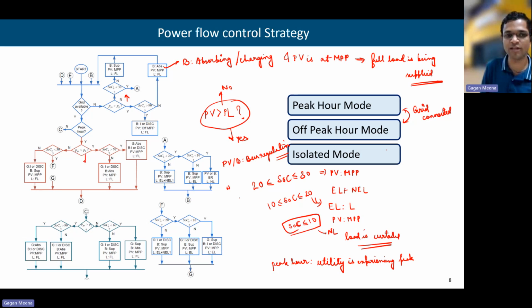If the load is more than the PV generation, then we need to check the storage because we don't want to take anything from the grid. If the SOC is less than 30%, then we need to check again the same thing. If SOC is between 30 and 20%, then the grid will be disconnected. PV at MPPT and the battery will supply both essential and non-essential load.